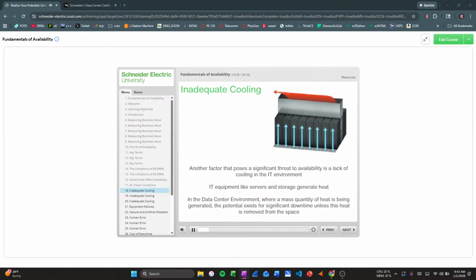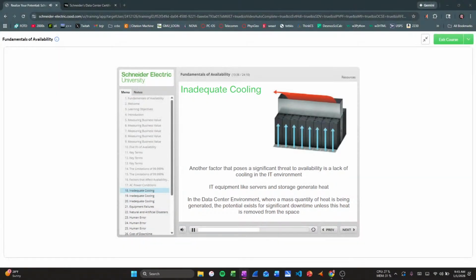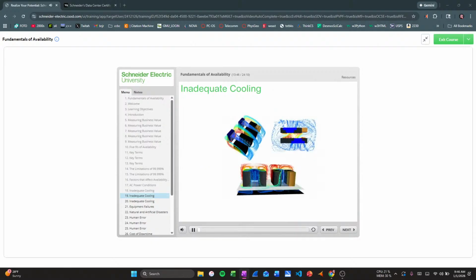Another factor that poses a significant threat to availability is the lack of cooling in the IT environment. IT equipment, like servers and storage, generate heat. In the data center environment, where a mass quantity of heat is being generated, the potential exists for significant downtime unless this heat is removed from the space. Cooling systems are needed in a data center to remove this heat. However, if the cooling is not distributed properly, hotspots can occur.